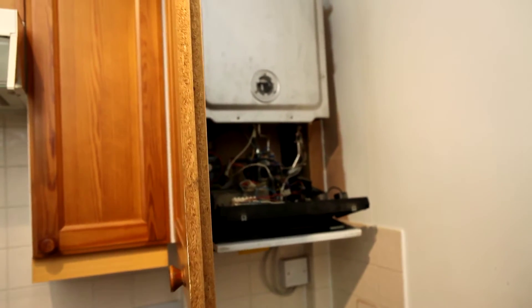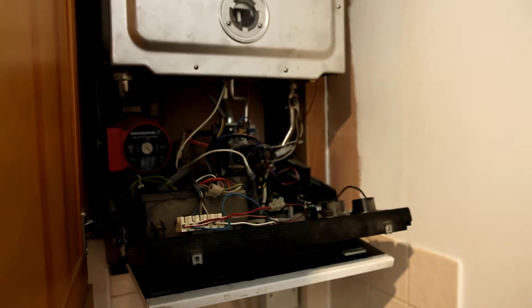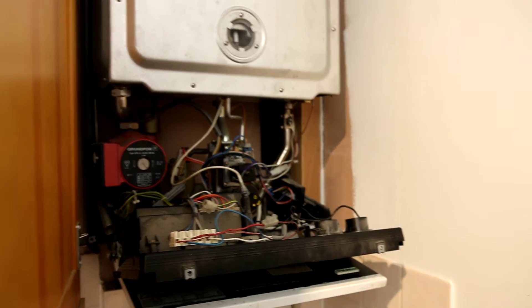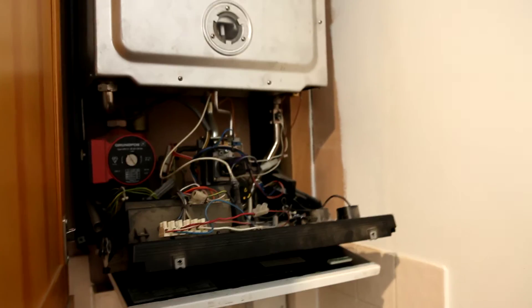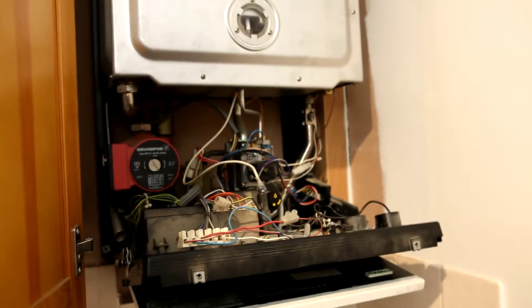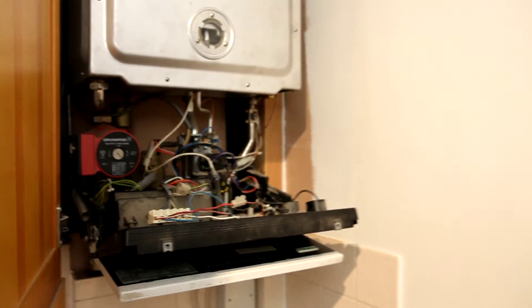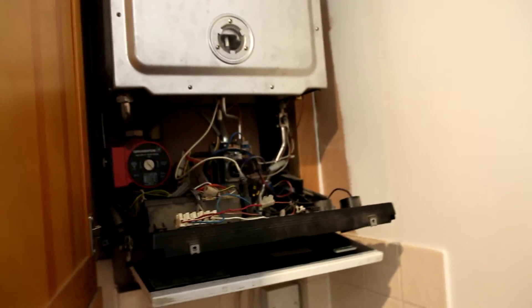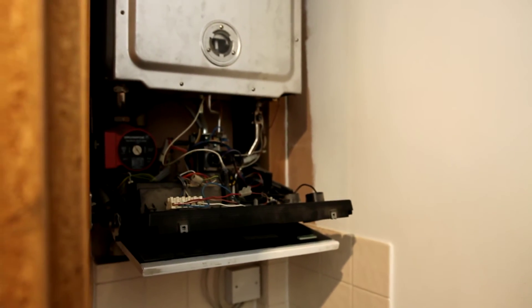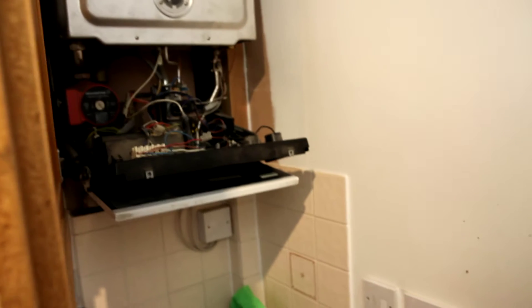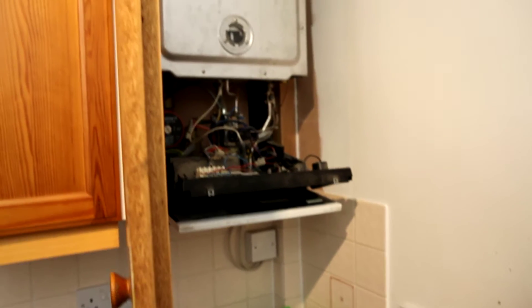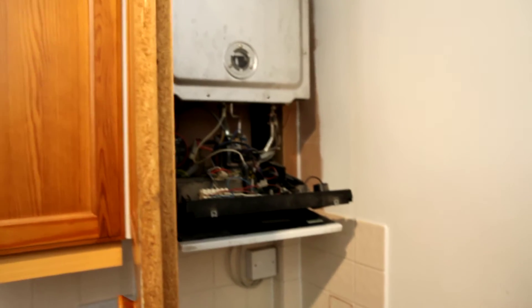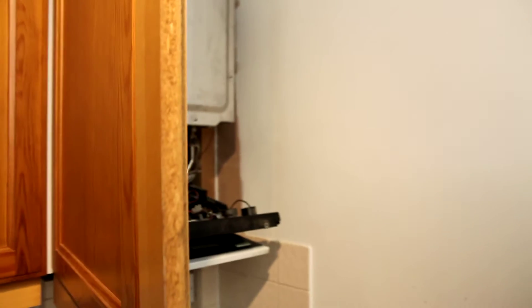So anyway, the boiler was incorrectly commissioned when it was last serviced. The poor guy that must have been living here before must have been really struggling with his personal hygiene, because the hot water is just completely unusable. So I'm going to go and shout at some of these gas engineers, Corgi, or Gas Safe, or whatever they're called, is the gas safety thing, and absolutely give them a rocket up their ass, because technically it's actually illegal for me to touch the gas regulation valve, but this is potentially a dangerous fault in correct gas pressures, and the fact that they would miss that during an inspection where I basically told them what the fault was is pretty disgraceful.